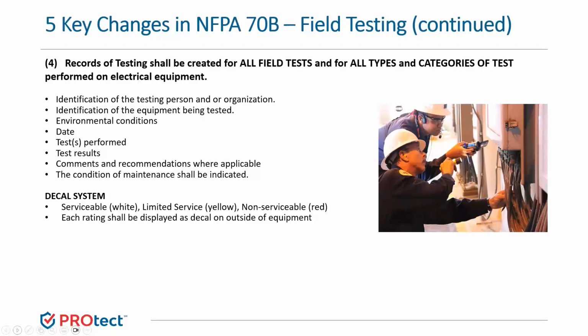So the field testing and test methods are also required to be included on the decal system. The decal system has some ratings as well. Serviceable is for any equipment that passes the test and is mechanically and electrically sound. That should be designated as serviceable with a white label. Anything with limited service is going to be equipment that has problems that are not detrimental to the protective operation or design, and that should be indicated with a yellow label. And then anything determined as non-serviceable will be equipment that has problems that are detrimental to the proper electrical or mechanical operation of that equipment, and that'll be noted as red. Each rating shall be displayed as a decal on the outside of the equipment. The date of the last inspection and the name of the inspector should also be included on that decal. And there's a lot more information in the code itself on what is to be included on that decal system too. So be sure to pay close attention to that.